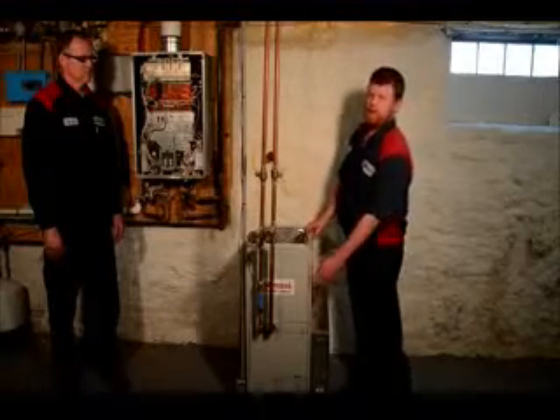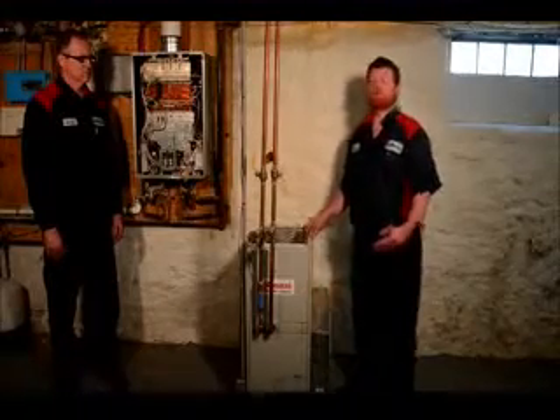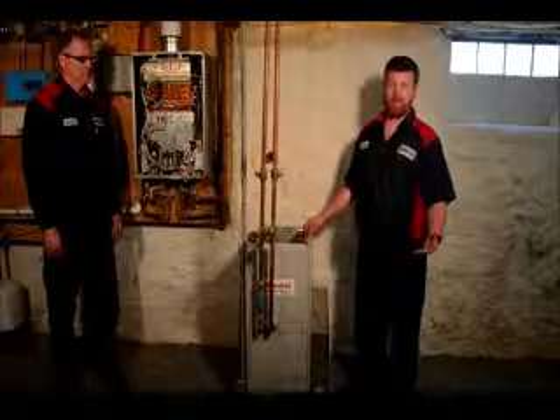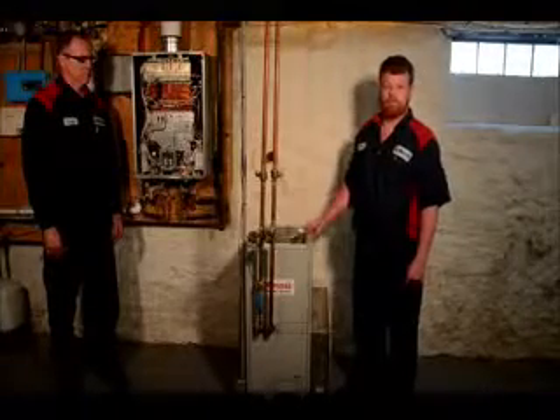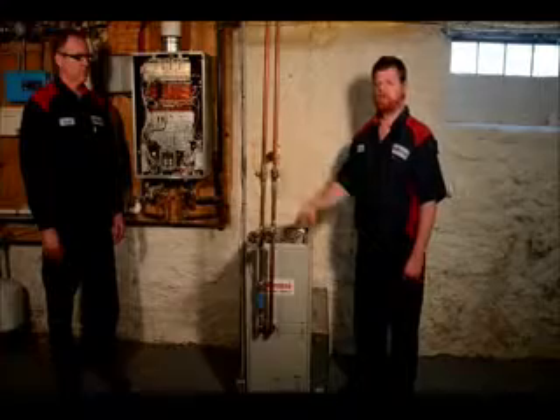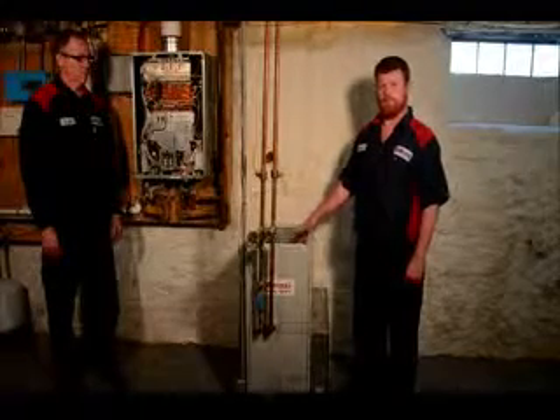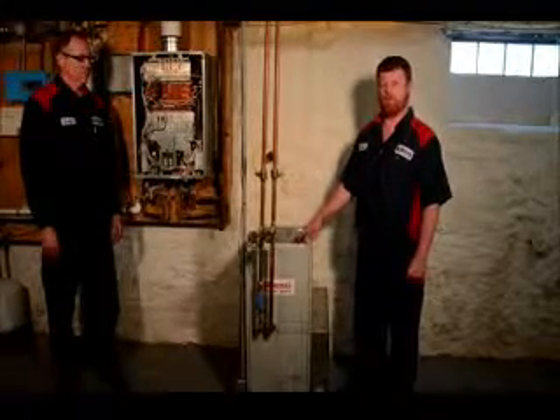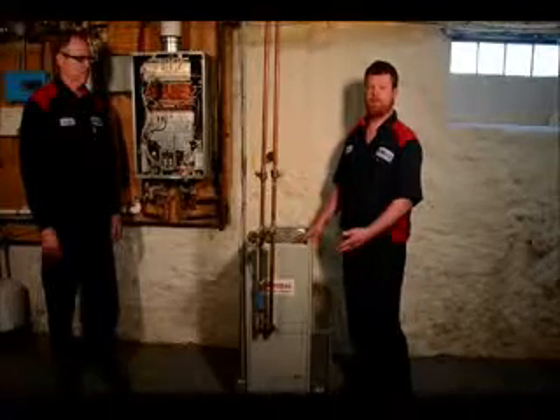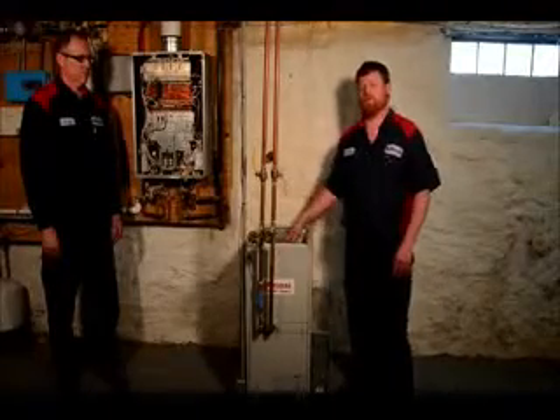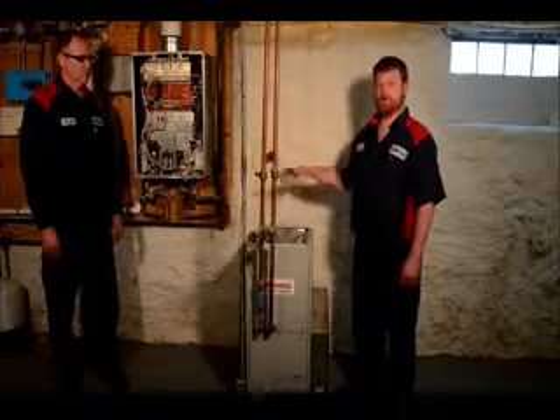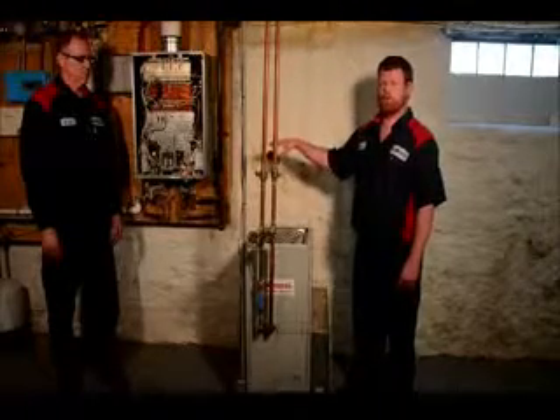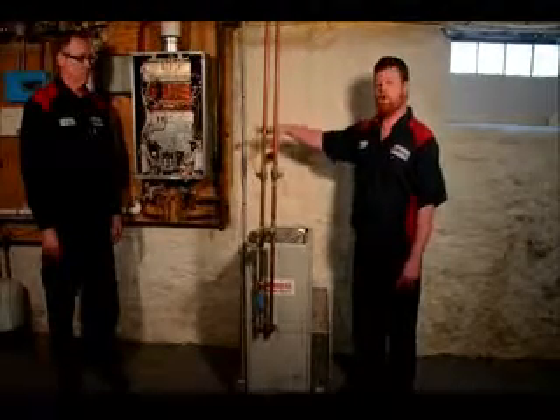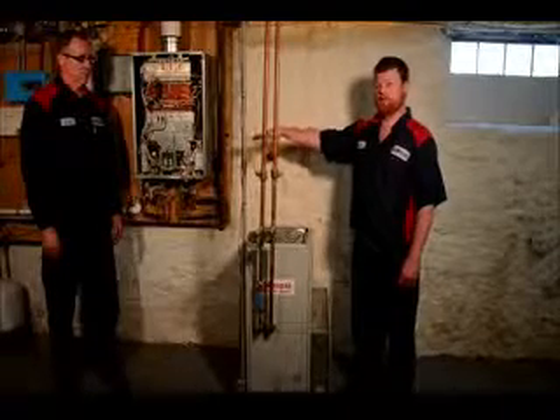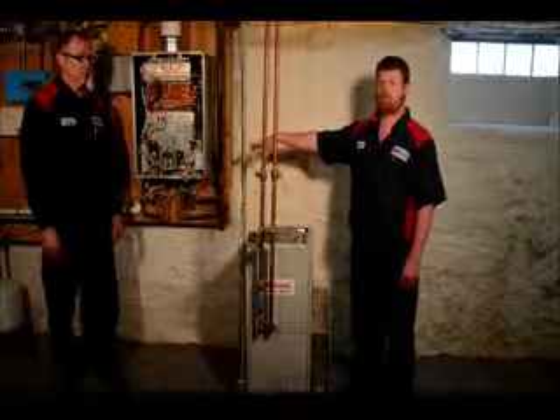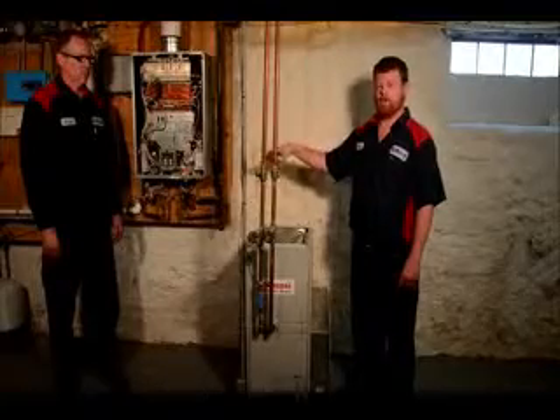This has a Taco 007 demand pump in it that is the industry-leading standard pump. This pump in turn drives the flow of that water heater, causing the heat to be driven through the coil. This furnace only has 4 mechanical parts. It has the blower motor, the PC board, the pump, and then the physical coil itself. As water comes through here, it will drop 35 degrees in temperature, putting heat into the house. The heated water's 35 degrees difference, versus the 70 degrees difference of the heated air you use in supply and return on air conditioning, is how you gain your efficiencies.